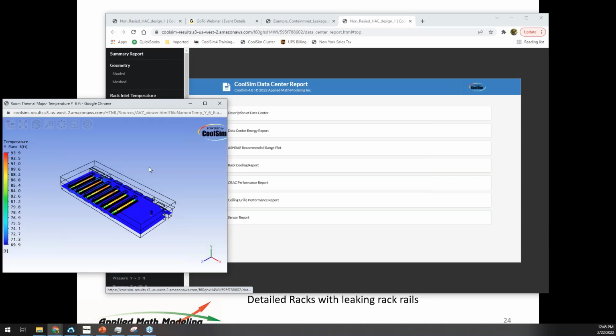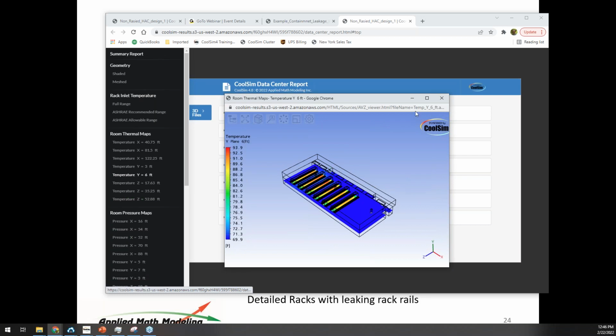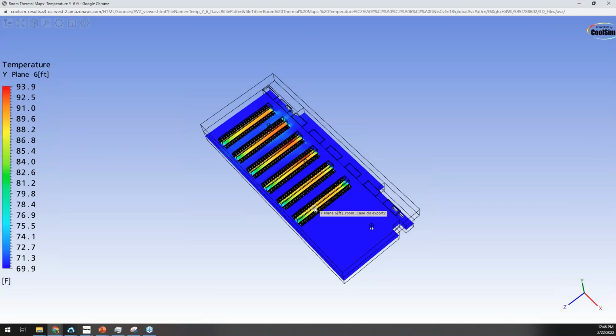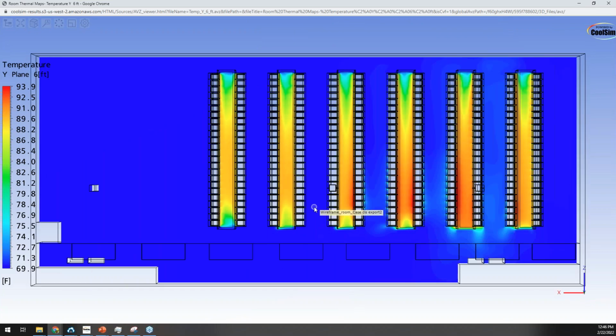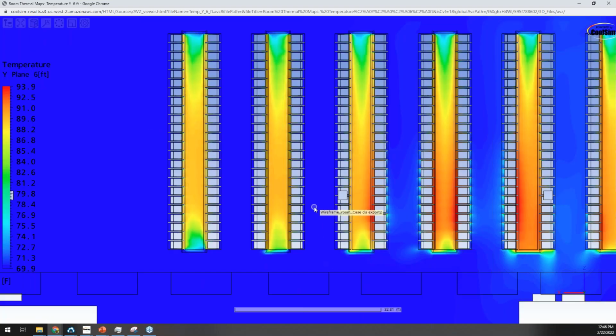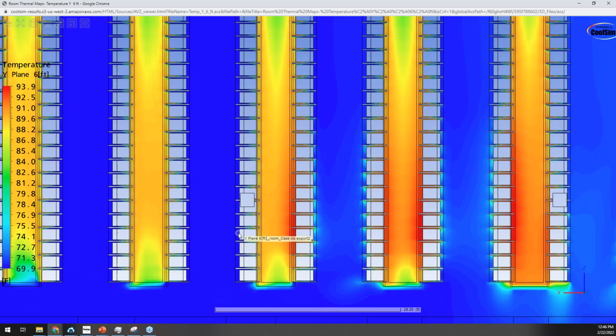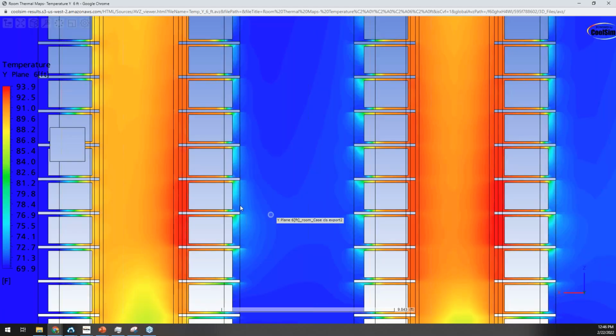I'm sure we're going to see a similar thing. I don't know what my supply air temp here is. I'll have to take a look. But we're going to see a very similar thing that we saw before in the model I just showed you. If we say this is a contour plane at y equals 6 feet, you see non-uniform temperature. If I take off perspective by using the N key, you can see exactly what's going on there.